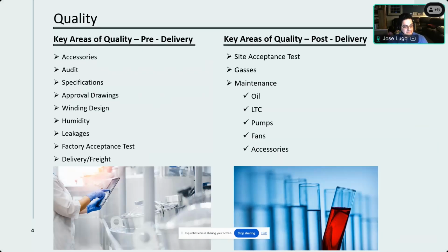You also have to go through the approval drawing stage. So you give money to a transformer manufacturer and they give you drawings and they say, does this look correct? You have to take a look at every single little thing and make sure that everything that they put in there is what you want. The winding design, again, you have to make sure that they're putting in the correct paper, the correct method of winding construction that you want to have in this transformer. There are many, many out there. The ones that are most famous are circular. Circular is definitely one of them.